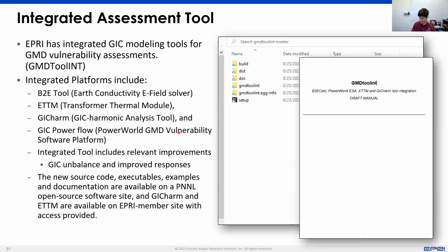It integrates the EPRI B2E tool, EPRI's ETTM, EPRI's GICharm, and the PowerWorld GMD solver, doing the GIC calculations plus the AC power flow that incorporates the increased reactive power consumption from the transformers.